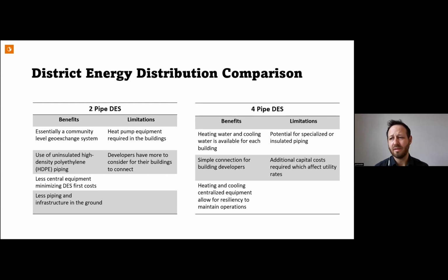The four-pipe system still has that potential as well, purely because it's providing heating and cooling at the same time. What you'll typically find, especially in modern district systems, is that they'll have heat pumps at the centralized level and supply a bit more chilled water as well as heating water, available at the buildings so they can accommodate that. So both still have the potential of handling it.